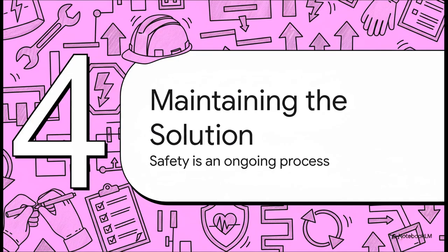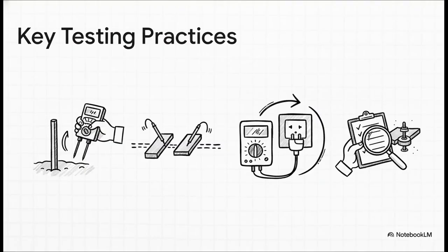That brings us to the final and maybe most important layer. You can have the most brilliant, safest design on paper, but if you walk away and forget about it, it's not going to stay safe. Corrosion happens, things get damaged. Safety is an ongoing job, and that means you got to get your hands dirty. We're talking about regular testing, measuring the resistance of those earth rods, making sure all the bonding wires are still connected, and checking that our breakers will still trip fast enough. It's a constant process of checking and rechecking to make sure everything is still working the way it was designed to.